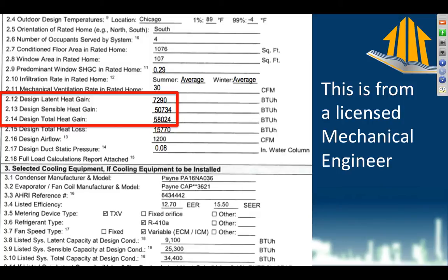But the design latent heat gain for this 1,000 square foot house is 7,000. The design sensible heat gain is 50,000. That means the design total, those two added together, is 58,000 BTUs per hour, which is a 5-ton air conditioner. Now when you see that the equipment they're actually selecting for this apartment is 34,000 BTUs per hour, there's a major discrepancy.